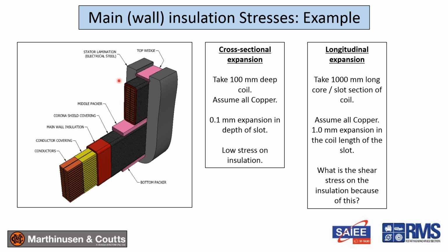So let's take an example. There's two types of stress that are going to occur: thermal expansion stress. The one is the cross-sectional stress. So in other words, the copper will expand in the height and in the width. The width is obviously very low, so we don't need to worry about that. Let's take an example of a 100mm deep coil. We assume it's all copper, and I think I worked on a 60-degree delta T. The expansion in the height of the slot will be 0.1 millimeters. So it's very little. It won't exert a major stress on the insulation at all. But if we take the longitudinal expansion and we consider a 1 meter long core, the expansion will be 1 millimeter in the length of the slot.